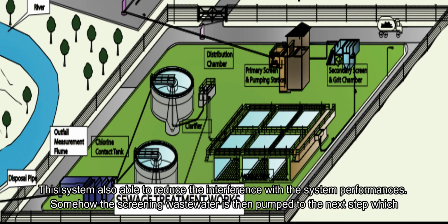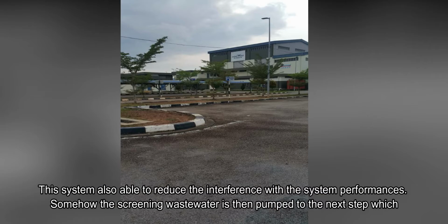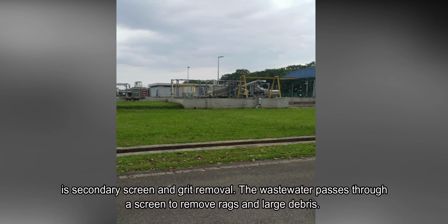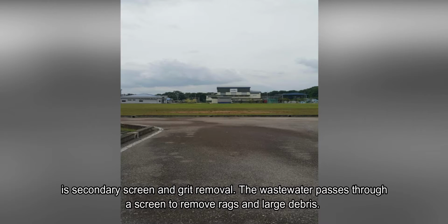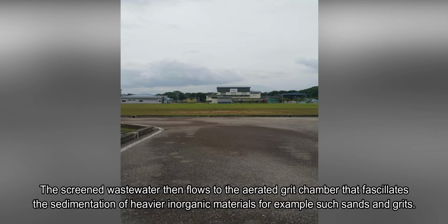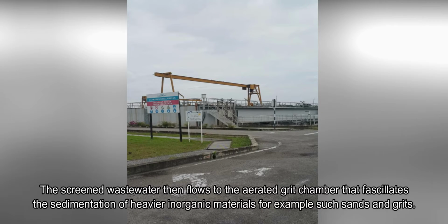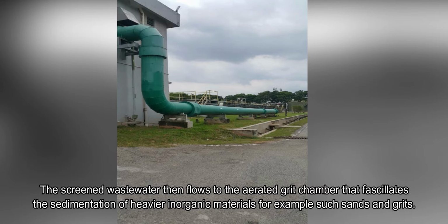The system is also able to reduce interference with system performance. The screened wastewater is then pumped to the next step, which is secondary screening and grit removal. The wastewater passes through a screen to remove rags and large debris. The screened wastewater then flows to an aerated grit chamber that facilitates the sedimentation of heavier inorganic materials, such as sand and grit.